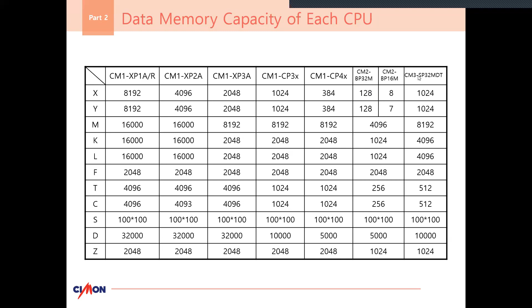These are a little bit about the maxes that each CPU could handle in terms of its device area registers. As we go from left to right, you can see that the number is trending downward. So that coincides with what we said earlier, that the XP is for larger products, larger projects excuse me, CP for moderate, and as we step down to the PLCS, moderate but small as well. I would recommend using PLC for small - do not try to run a PLCS for a project that a CP would be required for. And this has been discontinued, but we still do support, and will always support our legacy devices, because these are still floating around in the world. But typically these have been transitioned towards the CM3 series. We do still offer the block type, it's just under a different name.